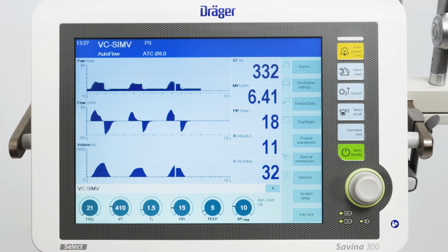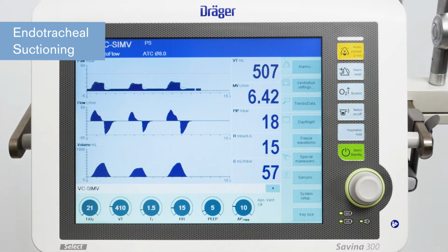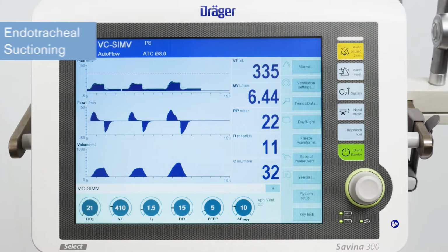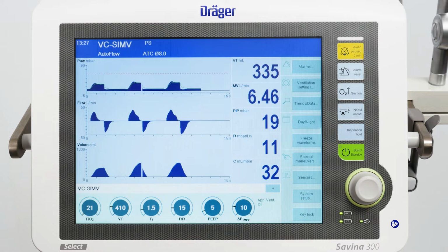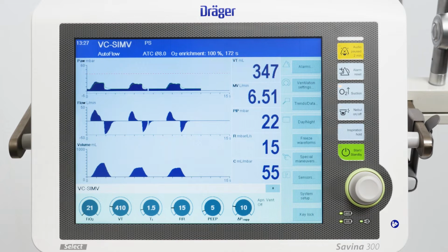To avoid any risk of hypoxia during endotracheal suction, Savina 300 Select offers a program for oxygen enrichment. During suction and for 2 minutes afterwards, the lower alarm limit for the minute volume is switched off. Press the O2 suction key. Savina 300 Select continues ventilating in the set ventilation mode at 100% volume O2.